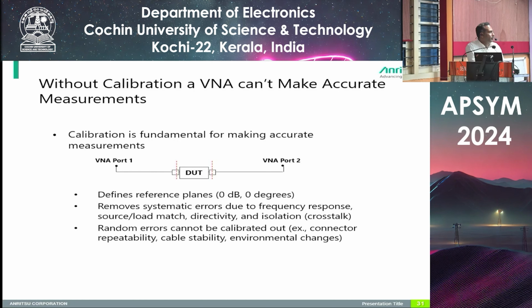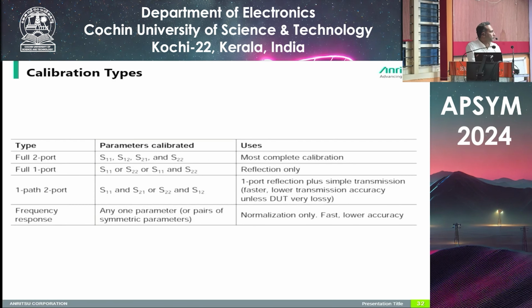And random errors, like connector stability, repeatability or environmental changes, occur when there is a repeatability change, when the cable stability changes, or when there are environment changes. So these random errors may occur. It may not be possible to calibrate them out because they may change every time, but we can remove the systematic errors, which are generated from the instrument itself, as I told. Okay, which are contributed from the instruments.